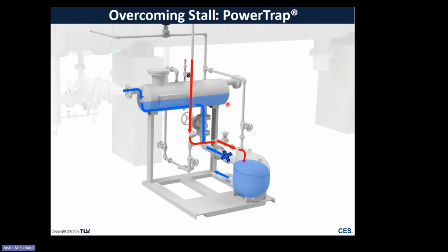Now part of the reason why this reservoir is here is to more or less act as a buffer so that we can back up condensate inside the reservoir and not back it up inside the process heater. As soon as all the condensate's pumped out, that internal mechanism is going to re-engage that valve assembly. It's going to allow that high pressure steam to exhaust, and it's going to equalize with the reservoir and equalize with the heat exchanger itself and begin allowing condensate to gravity drain back into the pump. That cycle is going to go over and over and over again.